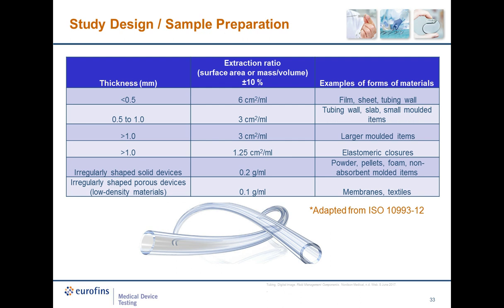The surface area to volume ratio can also have an effect on the extraction process. This table is pulled straight from Part 12, and it provides an outline of appropriate surface area or weight to volume ratios dependent on the type of device or material. Achieving these surface area to volume ratios can sometimes be challenging. Materials can be cut or crushed so that these ratios are met. However, when evaluating any type of coated material or material that might have surface properties different from the bulk material, cutting or crushing the material should be avoided.